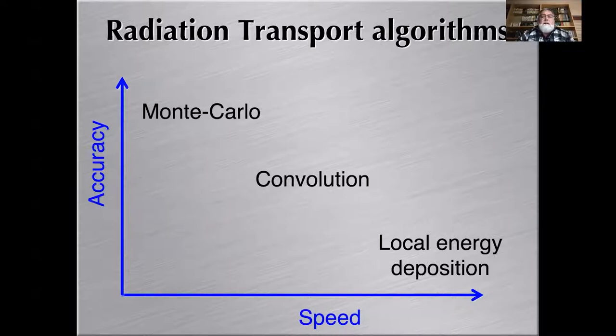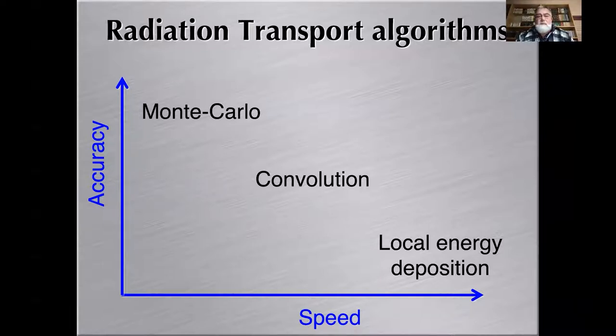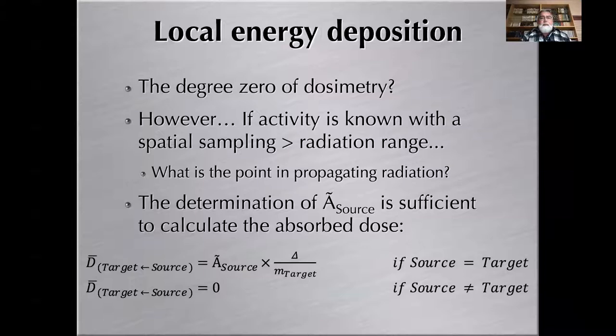There are three global radiation transport algorithms that can be implemented to compute absorbed doses. The first is local energy deposition — very quick, but only possible if you assume all emitted energy is absorbed locally. The second is convolution, which is mostly for homogeneous medium. The third is Monte Carlo, which is the gold standard because it provides an exact solution for absorbed dose calculation in heterogeneous media — but the penalty is computation speed, as Monte Carlo codes take a long time to run.